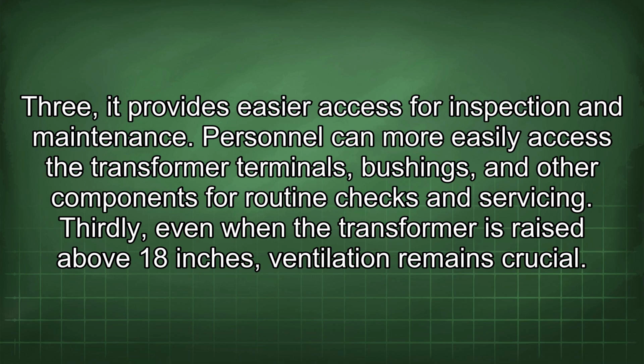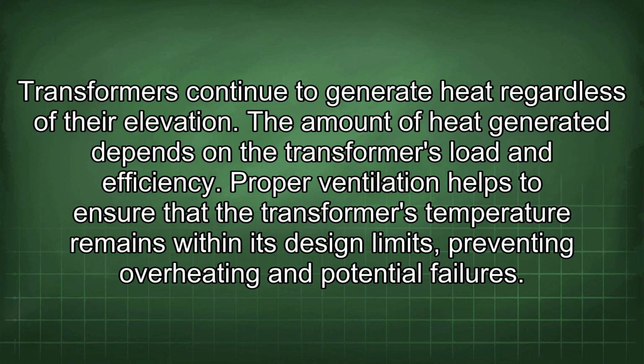Thirdly, even when the transformer is raised above 18 inches, ventilation remains crucial. Transformers continue to generate heat regardless of their elevation. The amount of heat generated depends on the transformer's load and efficiency. Proper ventilation helps to ensure that the transformer's temperature remains within its design limits, preventing overheating and potential failures.